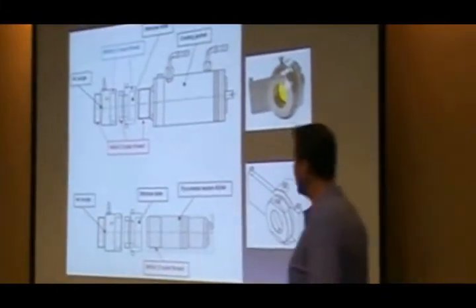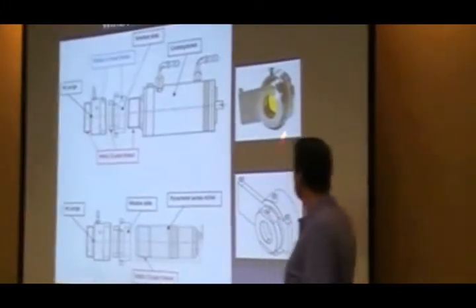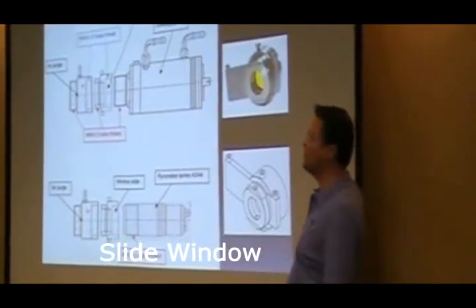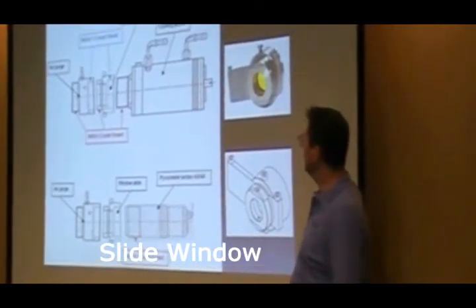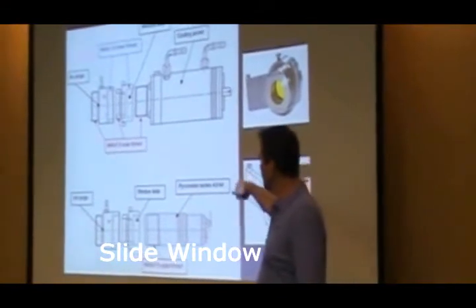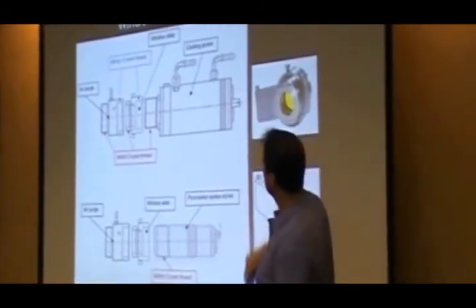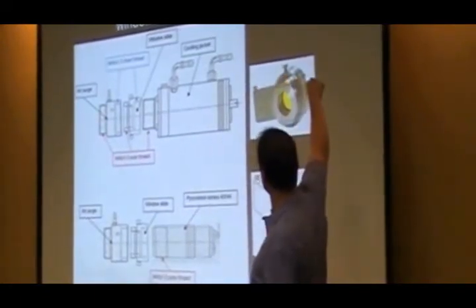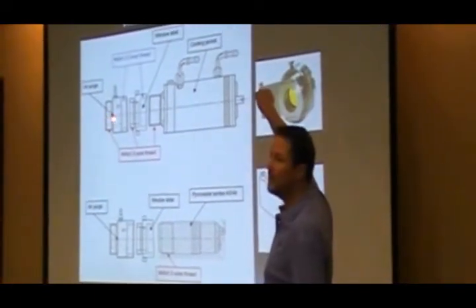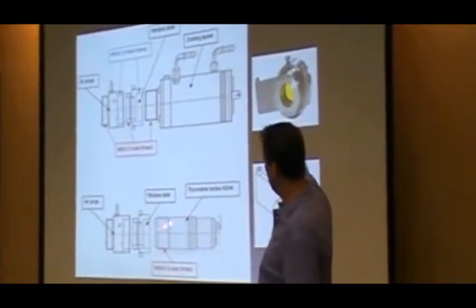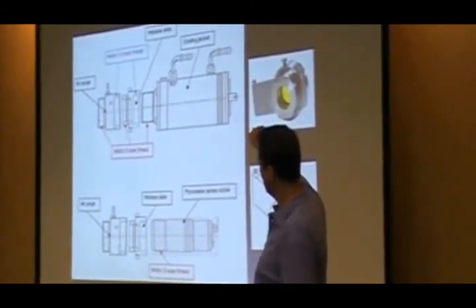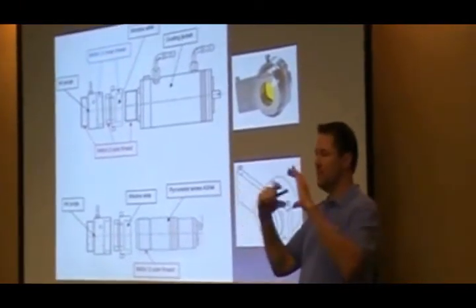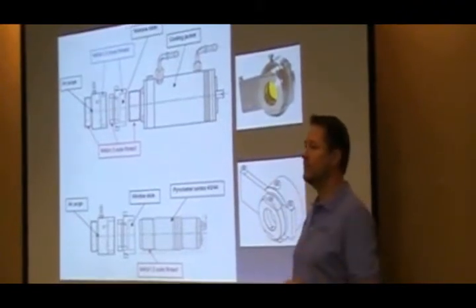About windows. On this particular jacket or the sensor, there is something called a slide window. This looks like a lead sulfide window or zinc selenide because it's yellow in color. This is an infrared window. So now you can integrate the window not only within the cooling jacket, it can be put on the cooling jacket, and then it has threads on the outside here. You could screw on the air purge in front of that, or you could just put it right on the sensor and then screw the air purge on that slide window. The windows slide in, slide out. So if you want to clean it, slide it out, clean it, slide it back in place in front of the lens of the pyrometer.